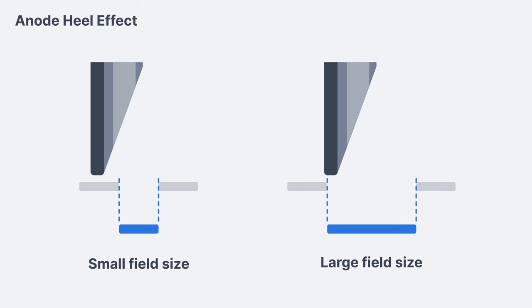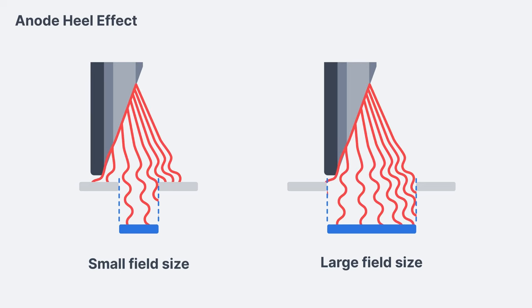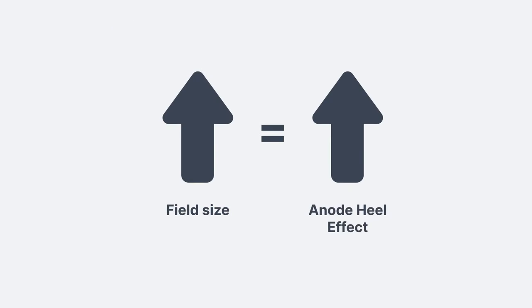The x-ray field size is one more factor that affects the severity of the anode heel effect. Increasing the field size increases the anode heel effect. Using a large field exposes the receptor to more of the low intensity beam on the anode side and more of the high intensity beam on the cathode side. This results in an increased difference in intensity across the x-ray field, which is the same as an increased anode heel effect. The relationship between field size and heel effect is direct — as the field size increases, the anode heel effect also increases.